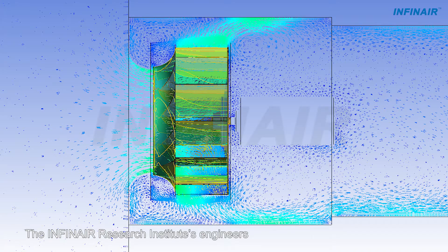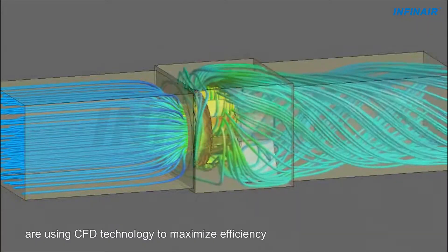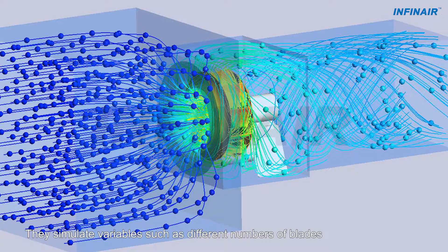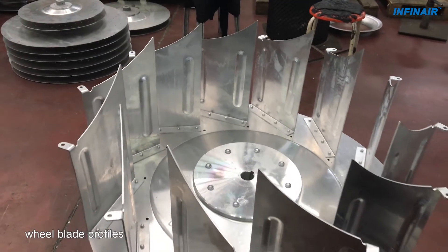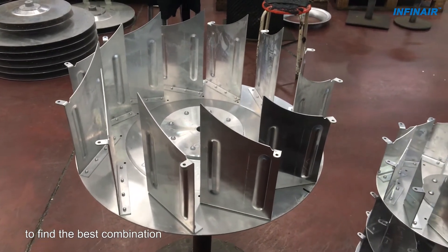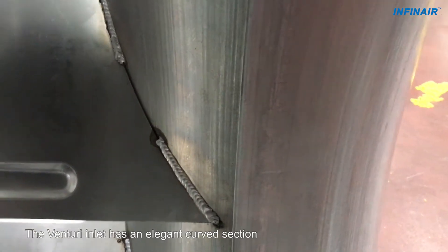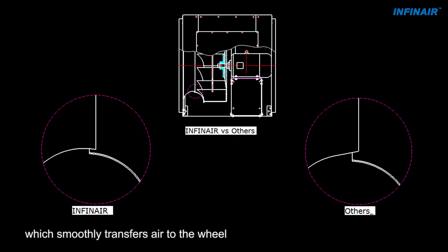The INFINAIR Research Institute's engineers are using CFD technology to maximize efficiency. They simulate variables such as different numbers of blades, wheel blade profiles, blade angles and lengths to find the best combination. The Venturi inlet has an elegant curved section which smoothly transfers air to the wheel.